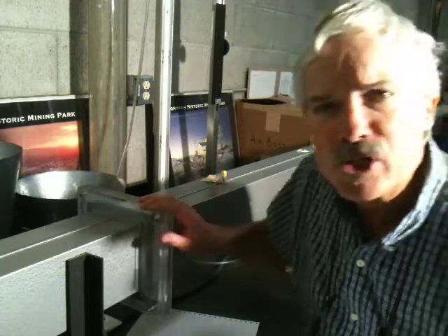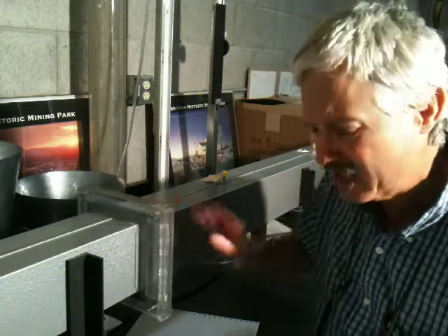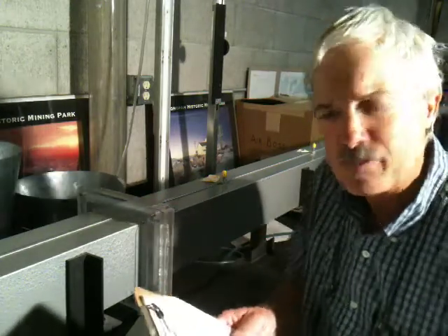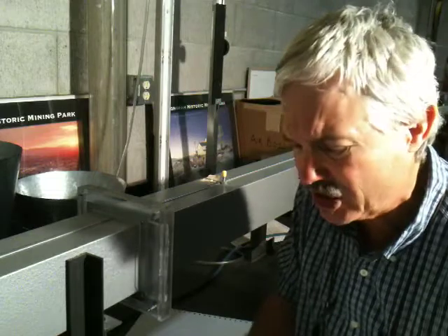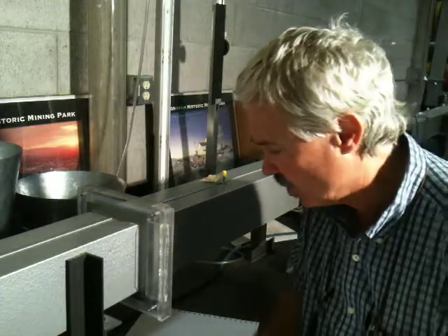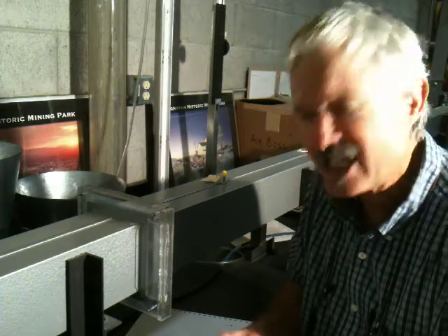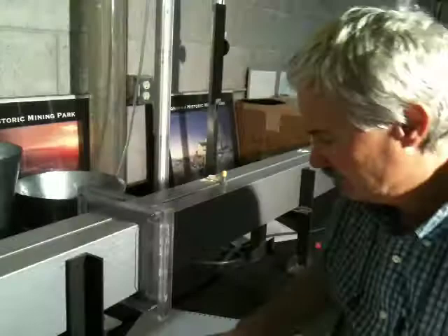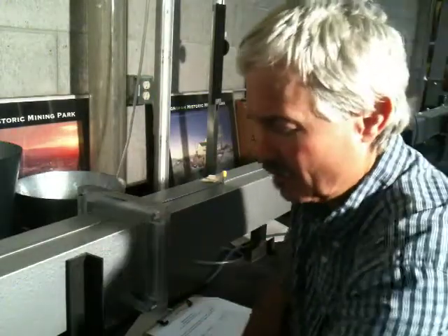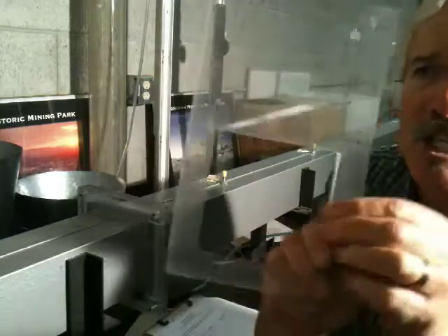I've got no restriction in place here, the blank piece. My centerline velocity pressure was 1.029 inches. Delta static pressure is 0.398 inches. So record that there. Okay. Now I'm going to go ahead and put in the first regulator, 3 3/4 inch size.